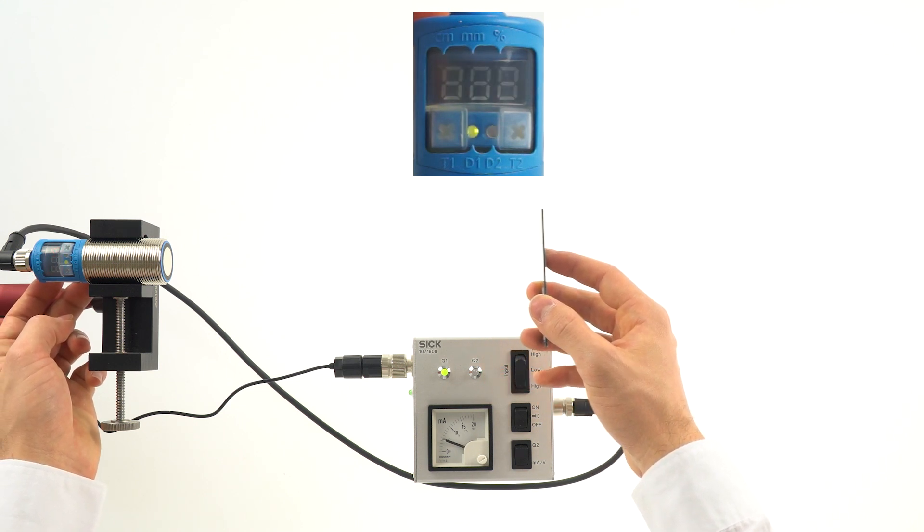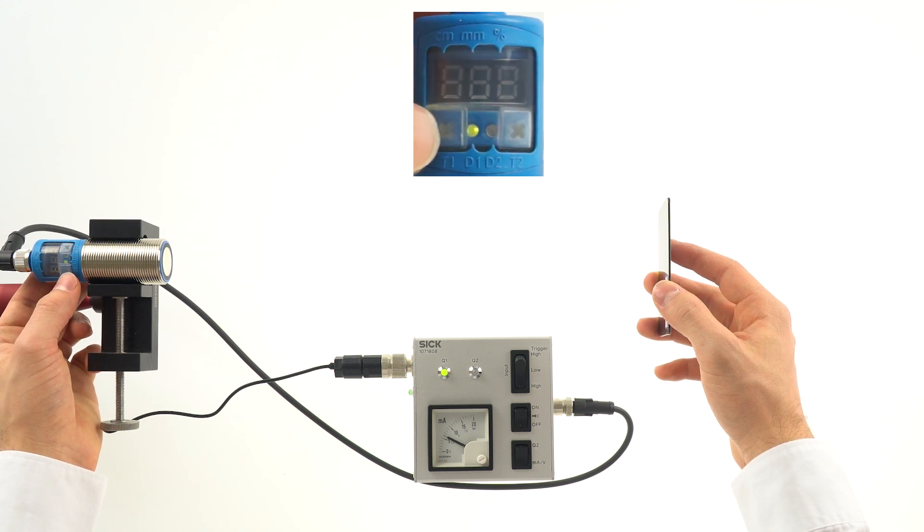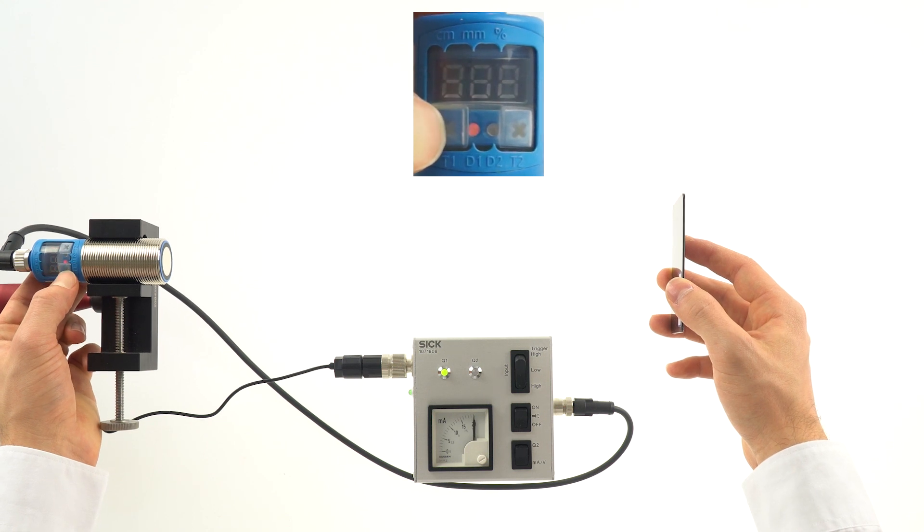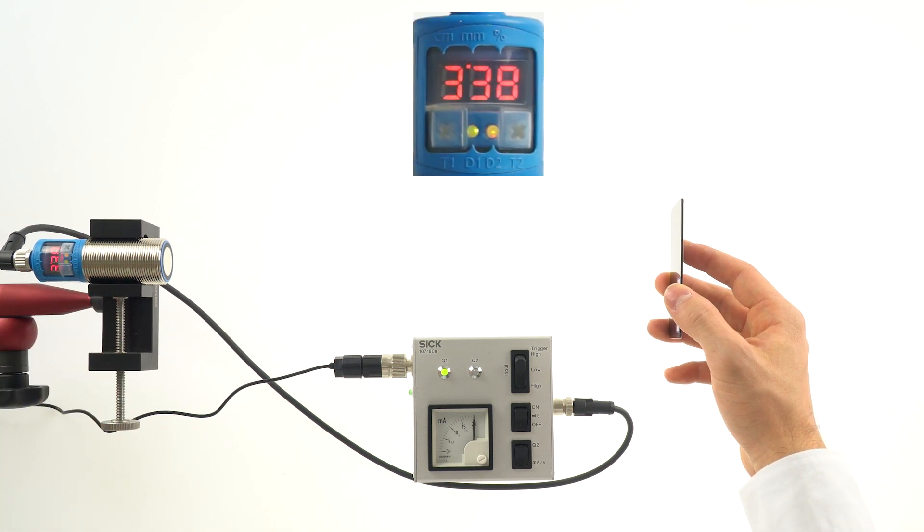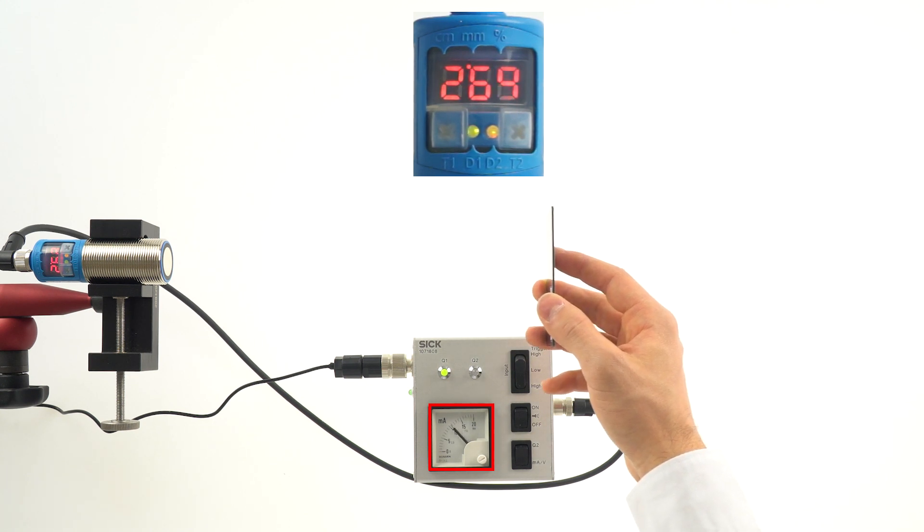Afterwards, place the object in a farther position as the far distance reference for the 20 milliamp value. Press and hold the T1 key until end appears in the display. The analog scaling is now saved.